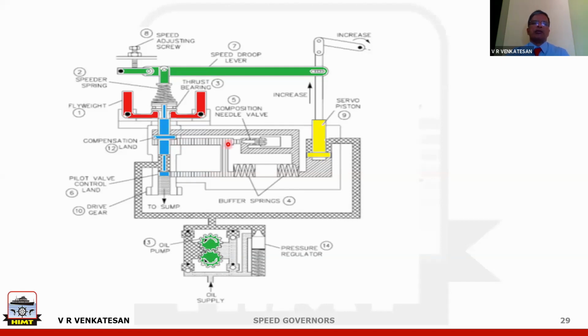The amount of negative feedback can be controlled by this valve called the needle valve. This is called the compensating needle valve. Suppose I open this valve quite a bit, then this oil will act on both sides, this side as well as this side. That means the compensation will be very little. If you reduce the compensation, then the governor will be sensitive and it will hunt. So the more I open this valve, the more the governor will cause hunting. If I tighten it, then it will become too much compensation and will result in sluggish behavior. If you tighten this too much, it will result in sluggish behavior.